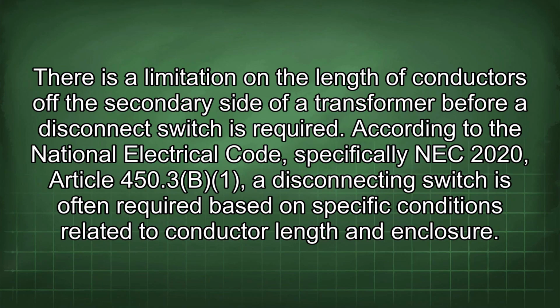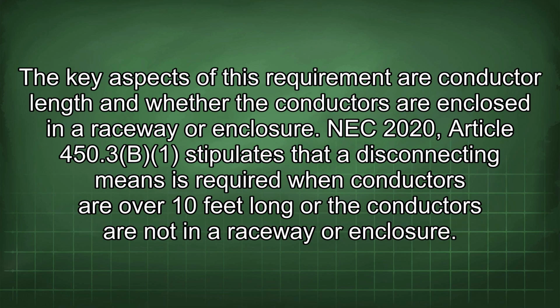There is a limitation on the length of conductors off the secondary side of a transformer before a disconnect switch is required. According to the National Electrical Code, specifically NEC 2020 Article 450.3(B), a disconnecting switch is often required based on specific conditions related to conductor length and enclosure. The key aspects of this requirement are conductor length and whether the conductors are enclosed in a raceway or enclosure.